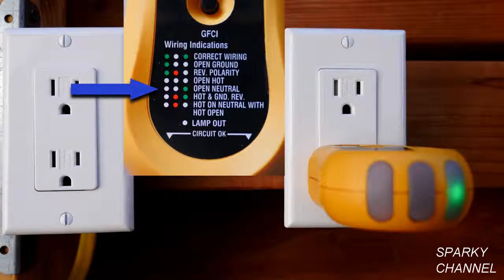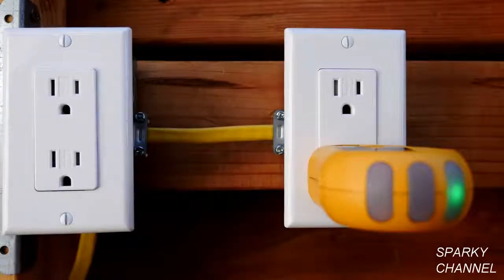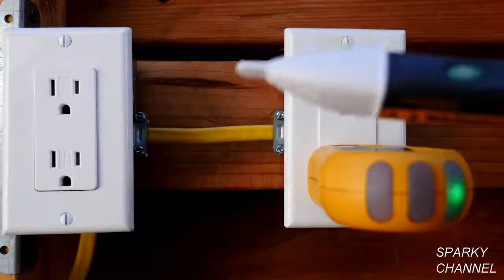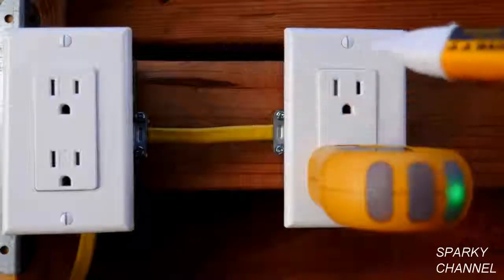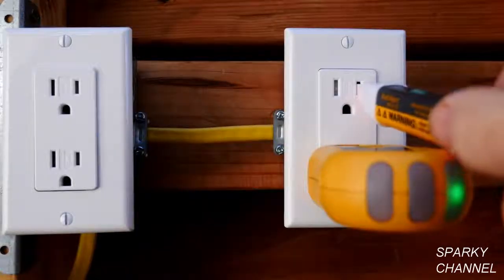The first thing I'm going to do is turn off the circuit breaker. But before I turn off the circuit breaker, I'm going to take this opportunity to test my voltage detector. See, it works just fine. You put it in the hot slot right here.